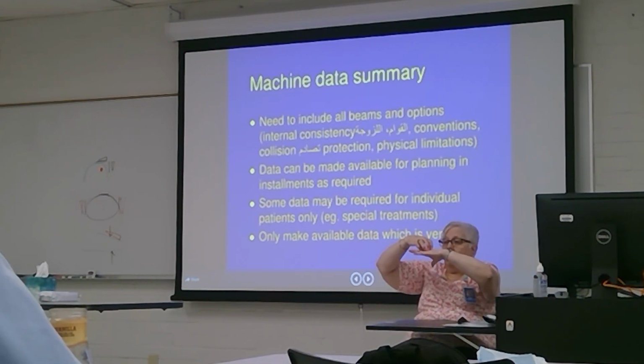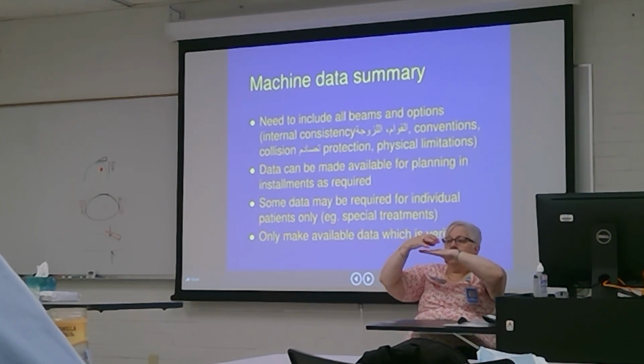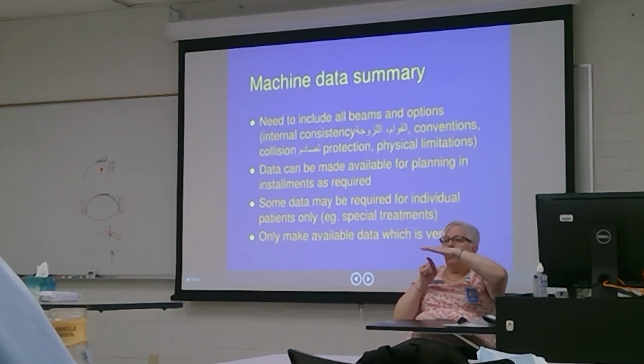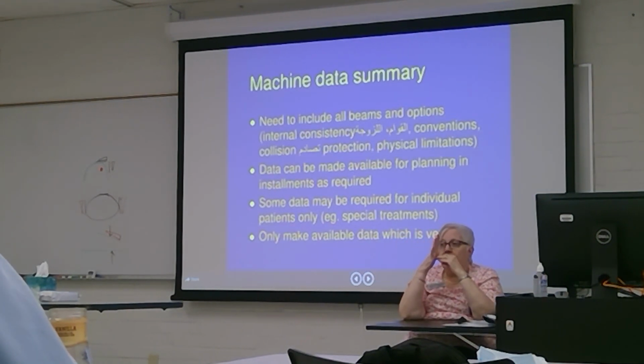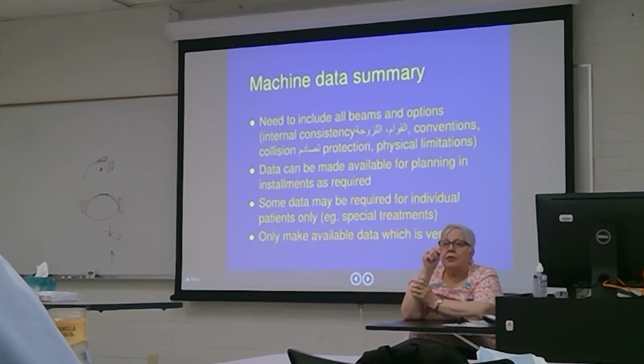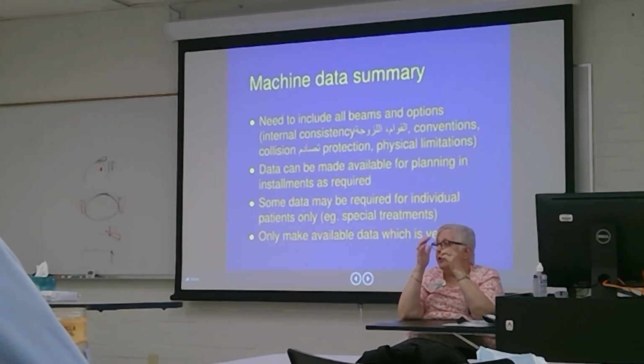If you have a patient on the bed and you're doing a planar field, a rotation this way, but they also want a non-coplanar arc this way, what happens when the machine comes up on here and goes dunk and it hits the patient? If you're not a therapist and you've got a Bachelor of Science degree and they've trained you to be a dosimetrist, you don't necessarily know that the machine won't do that. Or will do it, but it'll kill the patient in the process.